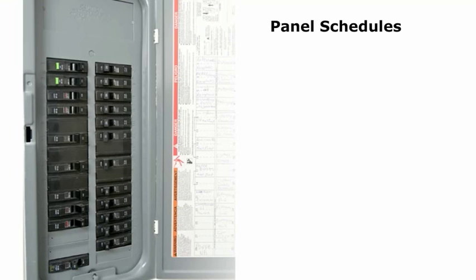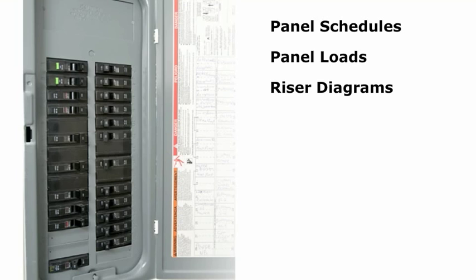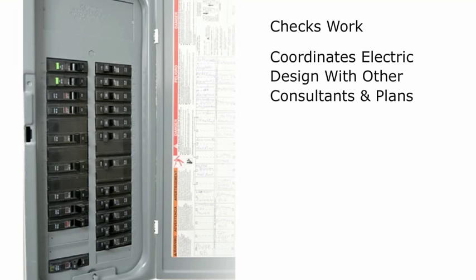Panel schedules are prepared that list all of the circuits for each panel, including those for emergency equipment. Panel loads are computed that show how much power is circuited through that panel. The engineer prepares riser diagrams that show how wiring is run vertically and designs the panels, switchboards, and service equipment. After computing the wiring sizes and protective equipment ratings, the engineer checks the work, then coordinates the electrical design with the other consultants and the architectural plans and continues to make changes as needed.